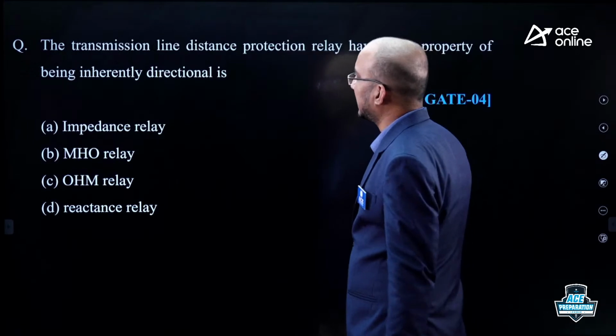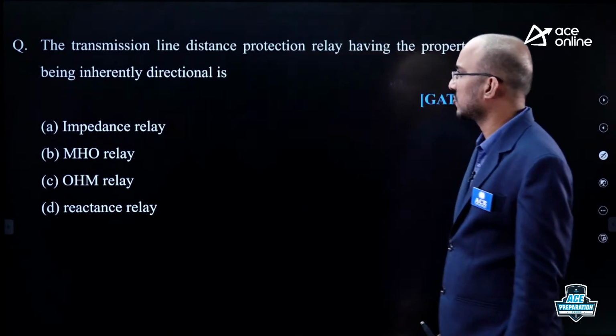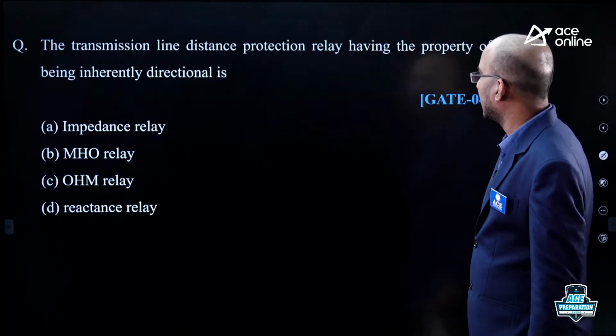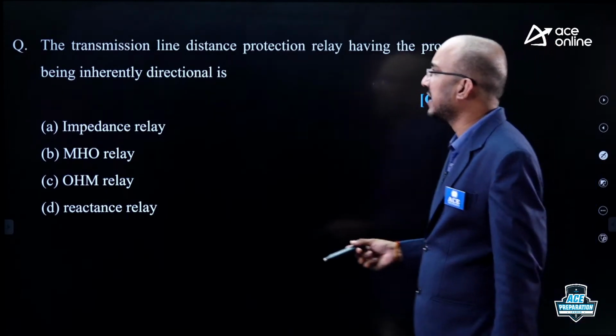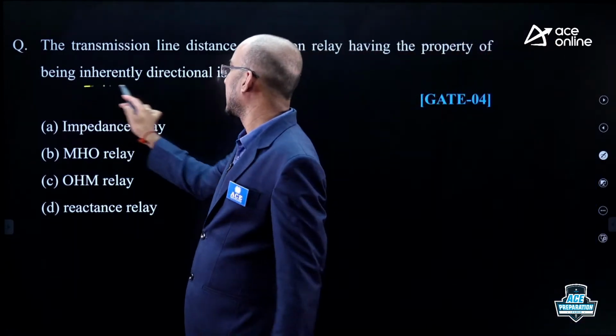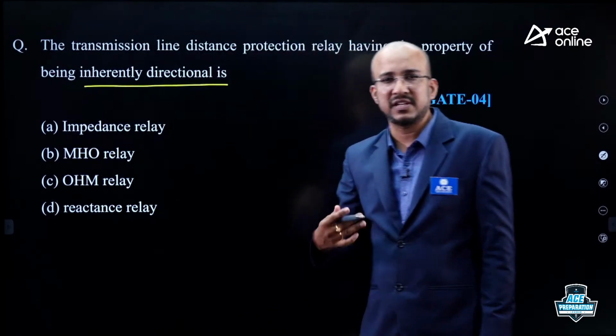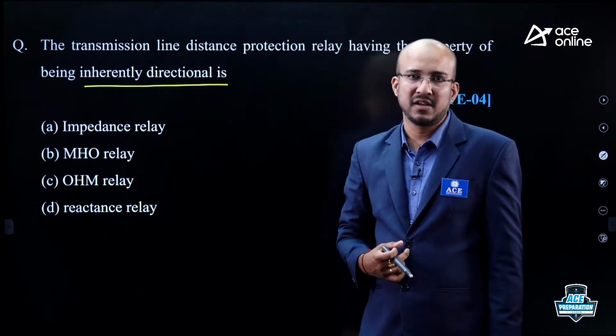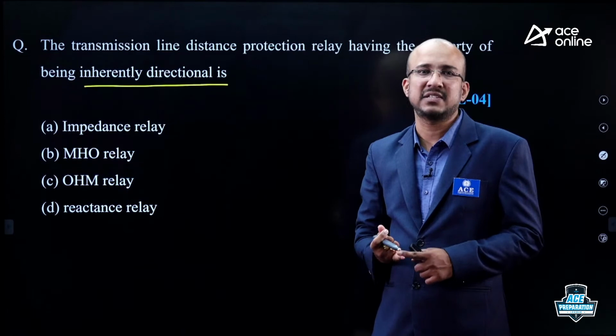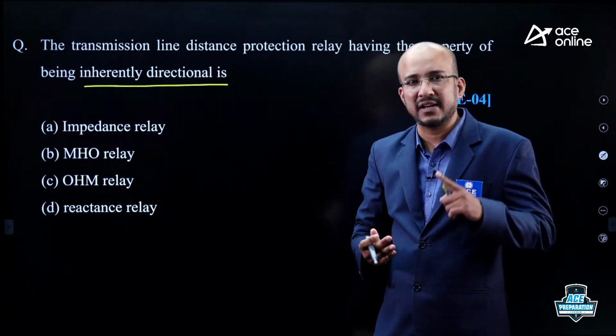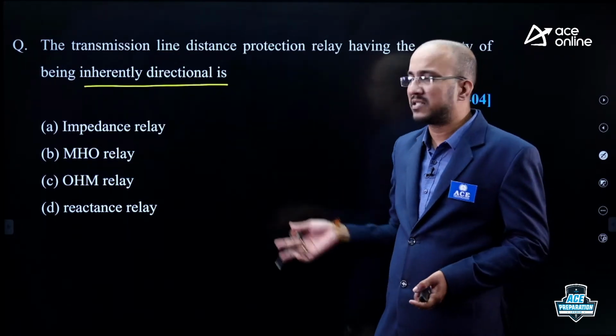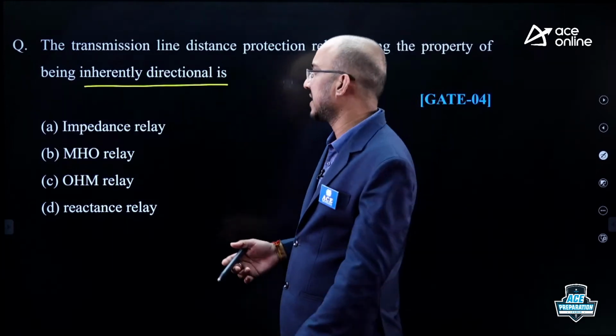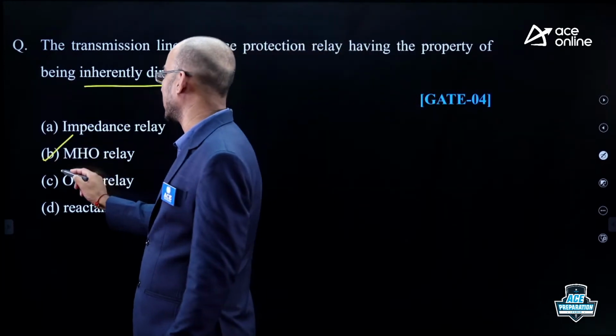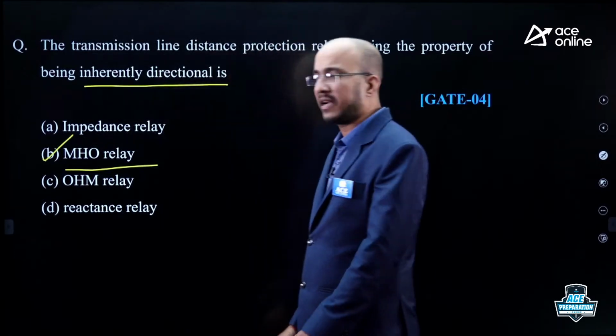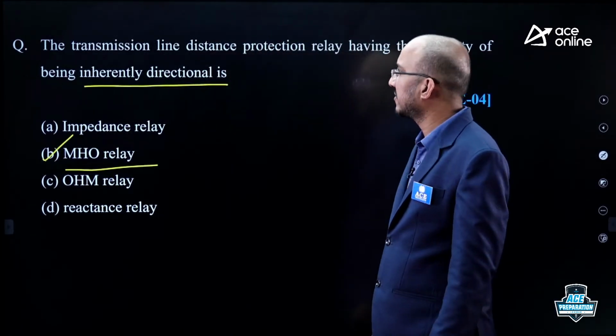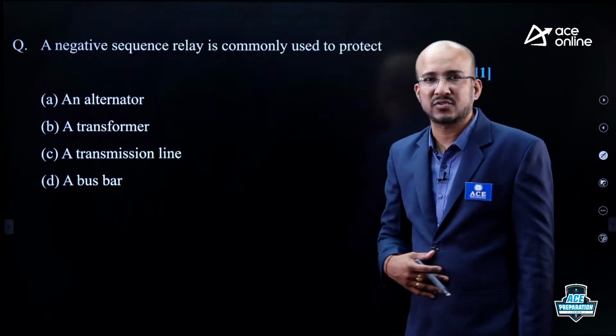Now observe here, transmission line distance protection. This is a question from distance protection. Which relay has the property of being inherently directional? We have three relays: impedance relay, reactance relay and Mho relay. Out of these three, the relay which is inherently directional is the Mho relay. Mho relay is inherently a directional relay. Okay. Now let us observe the next question.